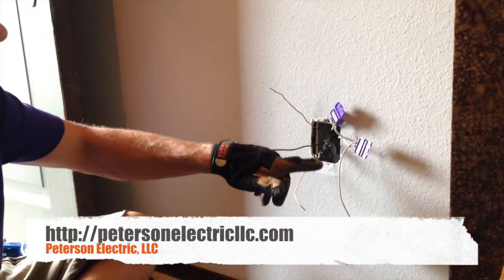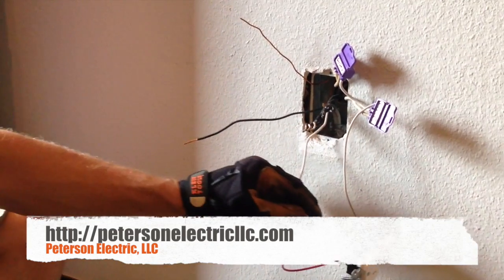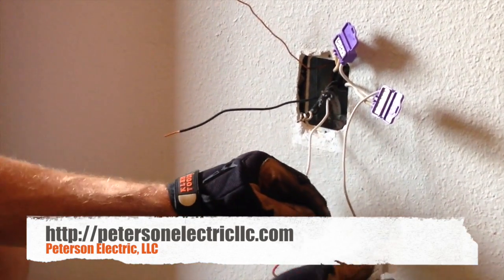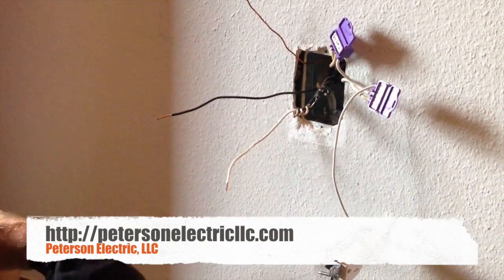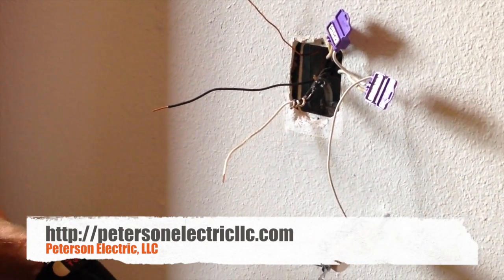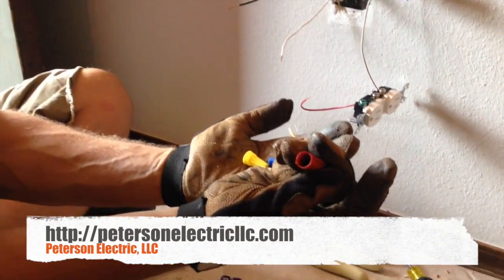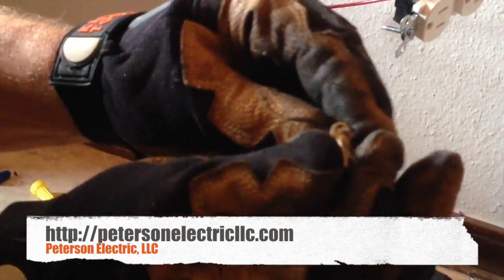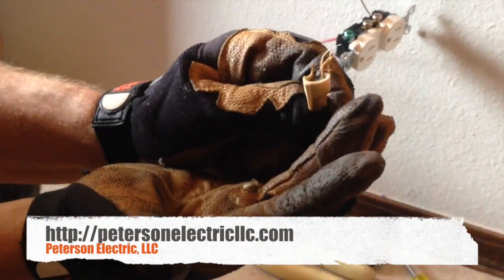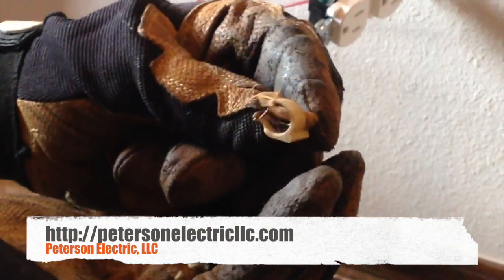The frustrating part is that this has got three aluminums and a pigtail for the copper, and another one that somebody installed a while ago. Your devices are only rated for copper, so that's why you have to use your AlumiConns. A lot of people think it's okay to squirt deox inside here, but here's the result of what happens when you do that. This tan wire cap is only probably within about five to seven years old.